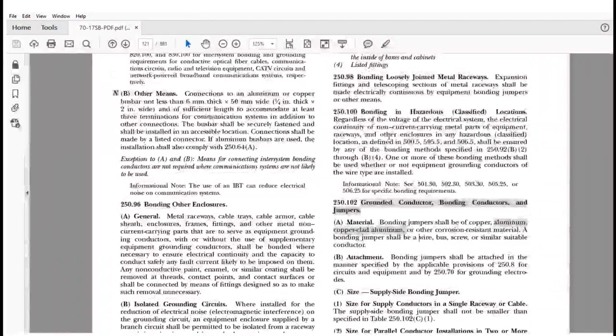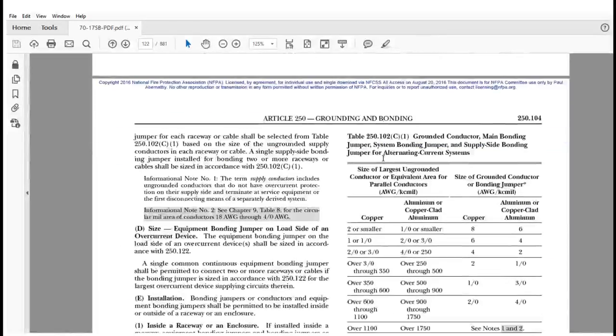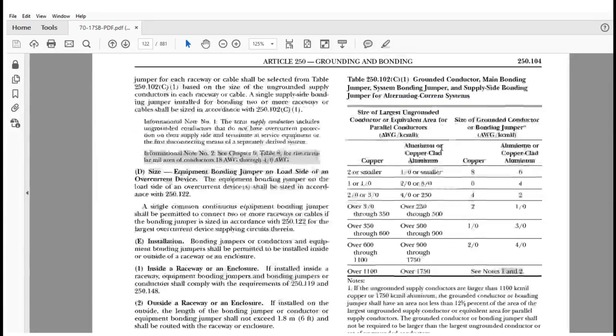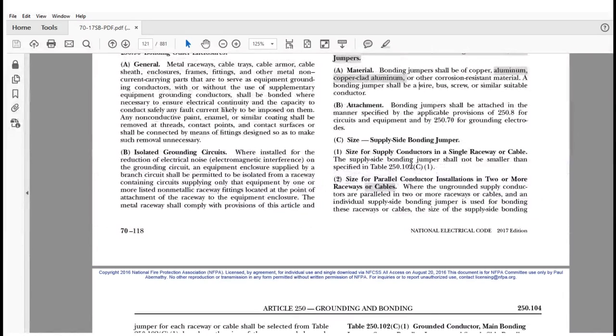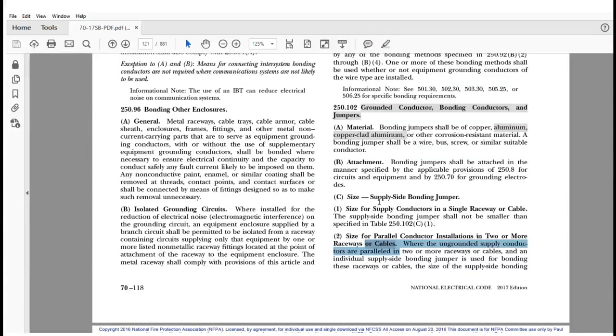The other change that I think is significant is that we need to know this application applies to cables as well. If I'm sizing, under 250.102(C)(2), parallel conductors installed in two or more raceways, it also applies to cables. In the previous code it didn't say that and it left you guessing, but inside the language it talked about cables, so people didn't know what to do.